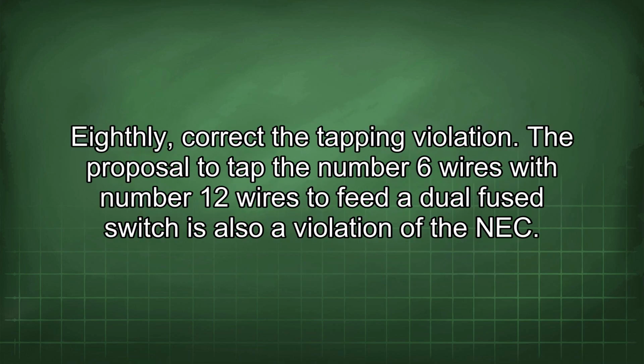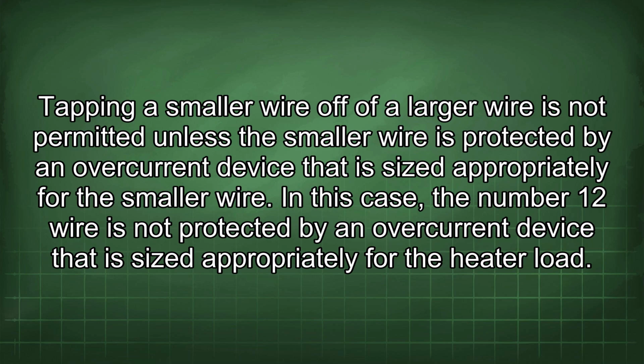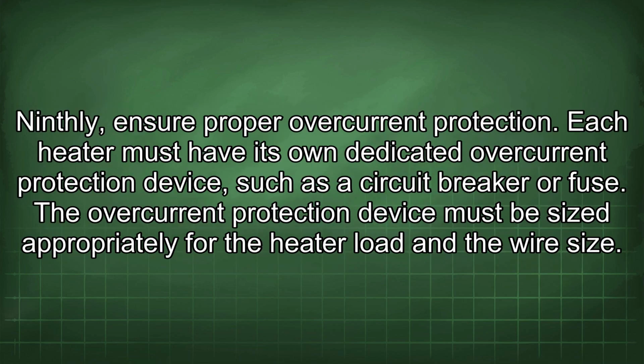Eighthly, correct the tapping violation. The proposal to tap the number 6 wires with number 12 wires to feed a dual fuse switch is also a violation of the NEC. Tapping a smaller wire off of a larger wire is not permitted unless the smaller wire is protected by an overcurrent device that is sized appropriately for the smaller wire. In this case, the number 12 wire is not protected by an overcurrent device that is sized appropriately for the heater load.